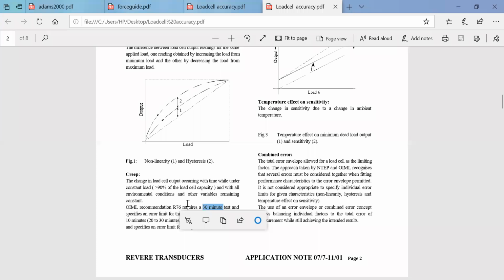So if you need to do it, we always need to set the applied load and wait for a particular dwell time. That could be 30 minutes, or it can also be between 20 to 30 minutes - meaning the minimum range to consider is 10 minutes and the maximum is 30 minutes. This is how it helps identify the errors. Based on the errors, you can classify how accurate the instrument is. So this is the best way to check the accuracy class of the given load cell, as per the European standards.